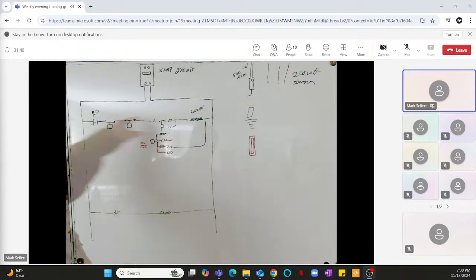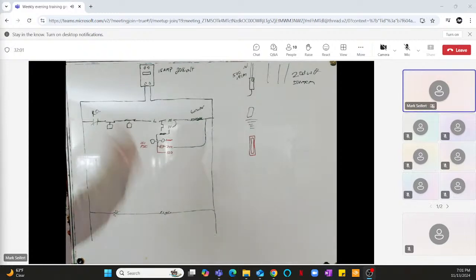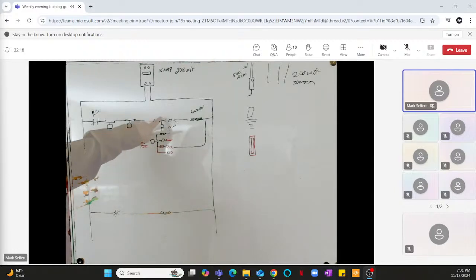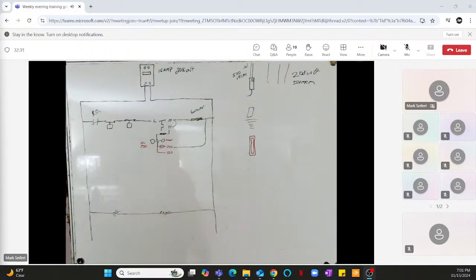So let's say it starts to run, the heater starts heating up, the compressor starts running, and the oil pressure gets high enough over the sump pressure that it pushes this circuit open. Now no more current is running through this circuit, and it's not going to trip. That's how they work. They're cool little devices. The guys back in the day, man, they knew what they were doing. They really did. Nowadays, you got the Sentronic that literally gets rid of all this stuff and just makes it a switch here, just a switch like a relay output. It's got the electronics that does all this old school stuff. But it's that easy. There's nothing more scientific about it.